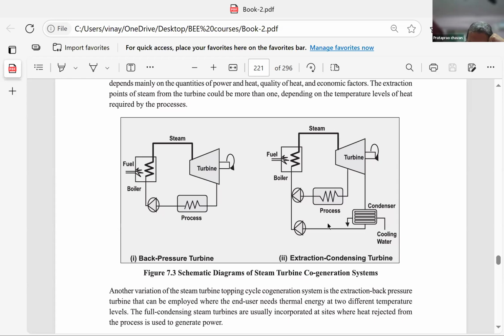Here we are compromising the efficiency, but we are allowing more electrical generation than here. Same steam, same pressure and temperature parameters. Here it is allowed to work completely for generating electricity and is exhausted here. Here there is no electricity generation; it is directly exhausted to the process. Electricity generation is partial, not full: partially electrical generation, partially process work. Here also there is partial electrical generation, but the quantity of electricity generated is more and a smaller portion goes to the process.